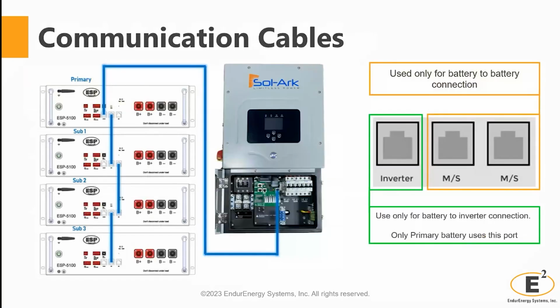Once you finish setting up the DIP switches in the batteries, you will need to connect your communication cables. Those communication cables are included with our BU units, and it's pretty simple. You will receive a bunch of different cables, and those cables are normal Ethernet cables that you connect between the batteries.